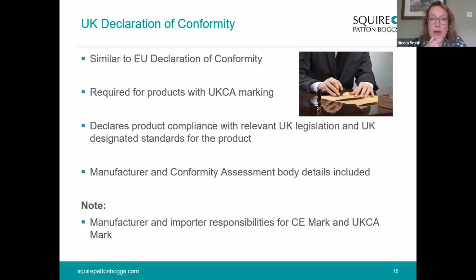That will, of course, be slightly complicated by the fact that where requirements are governed by a regulation in the EU rather than a directive, those regulations have come into UK law at the end of Brexit because they've been grandfathered over, as I say, automatically. So you may still have the EU law on your Declaration of Conformity for the UK in those circumstances, because the retained law will have the same title, and it will just say at the end, in brackets, retained law. But as I say, it's just important to make that distinction because that is going to be the document that is available to enforcement authorities.